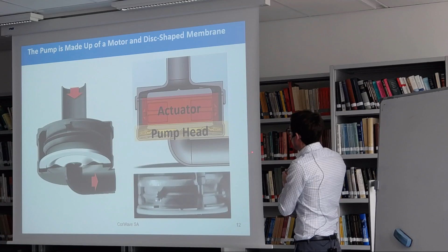The blood flow comes from the top, from the heart, and makes its way around the actuator, which is sort of a cylinder. The blood flows around it until the edges of the pump head where the membrane is fixed, and then it is accelerated towards the inside where there's an outlet, and the blood exits through here.